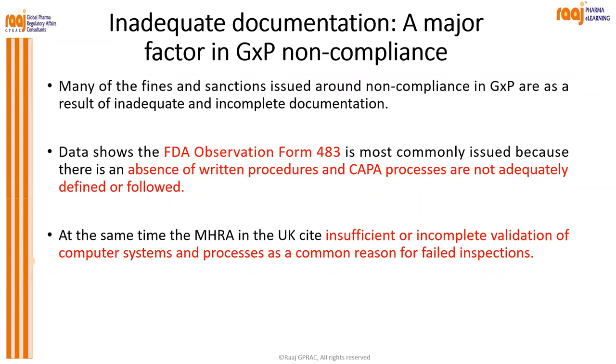As I said, validation, risk-based approach, documentation, including CAPA, is very important. How you take the corrective and preventive action, so that the same thing does not occur again. The reoccurrence is avoided by way of prevention. So how you prevent, how you take the precautionary measures, you have to define in your procedures.